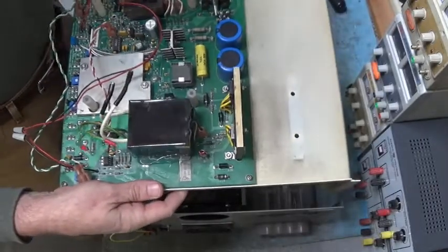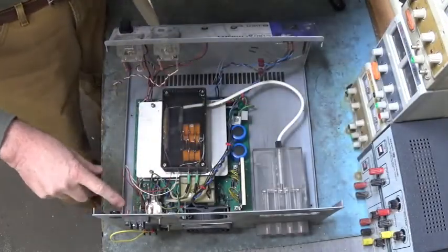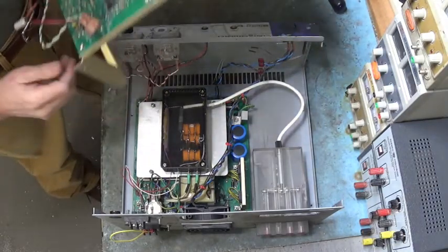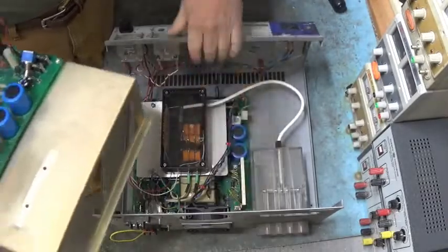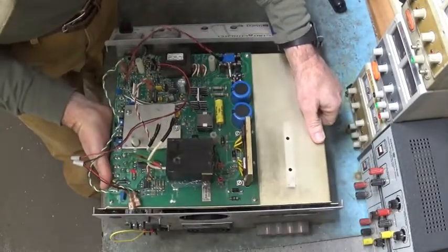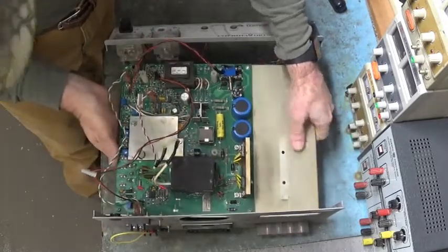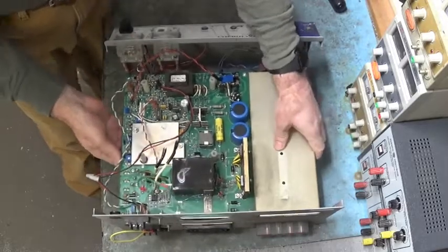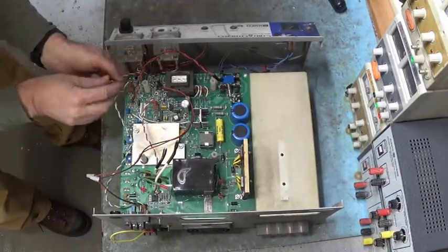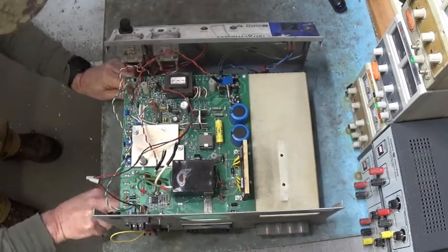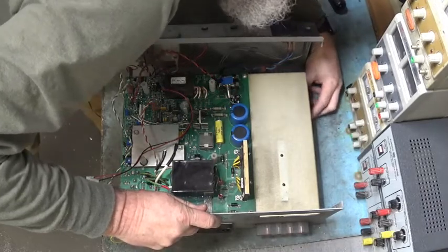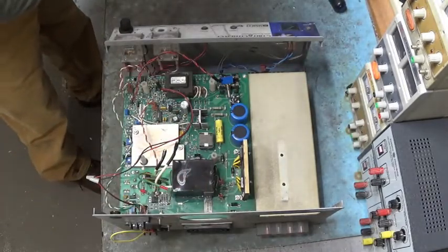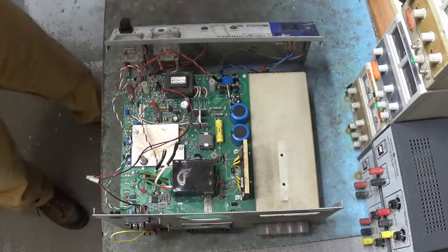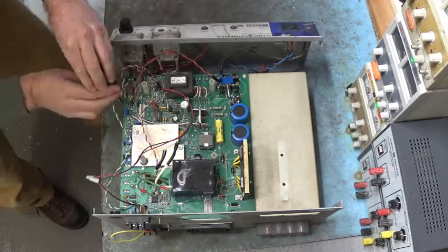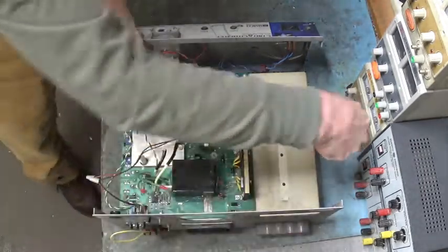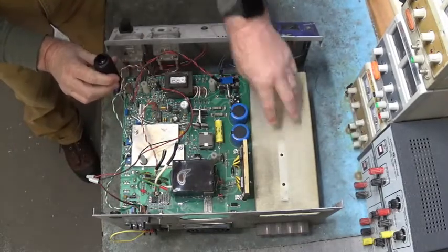Let's put all this in the cabinet. This is a little bit tricky because here's our enable terminals and here's our meters, and they always get in the way, so you have to pry the walls apart a little bit when you're going in. There we go. Just clear the meters right there. Okay, let's make sure we're not crushing any wires on the positive side. There we go. We okay on that side? Okay, we're all clear on that side. Now we're going to install the plate mounting screws. There's 2 on this side, there's 2 on the back, and there's 2 on the other side that hold this plate to the housing.